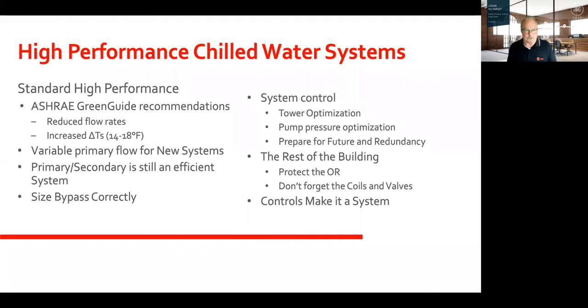So in conclusion, we've kind of stressed the importance of a high performance chiller plant, and touched on the guidelines that ASHRAE has been changing, increasing delta T rates, variable primary flow for new systems, and primary secondary is still a good way to go. We want to make sure that you're sizing those bypasses correctly, or if it's an older plant, make sure it is sized properly, because you can get big savings by just correcting a small piece of the piping in the chiller plant. Tower optimization and pump pressure optimization are other components of the entire chilled water system that can help increase the efficiency of your building and your cooling needs.